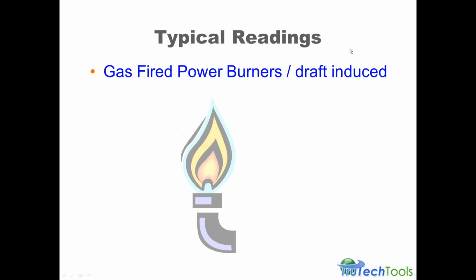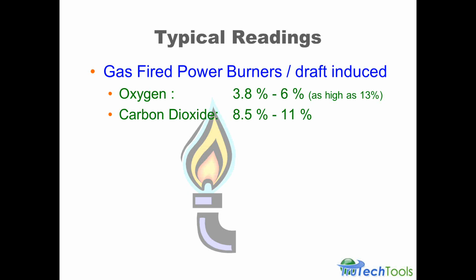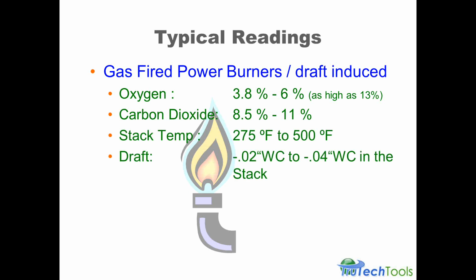On a draft-induced or power burner, the oxygen numbers do vary a bit, and here they're moving between 3 to 6 and even as high as 13% in some situations, higher levels of oxygen, with lower levels of carbon dioxide between 8.5 and 11%. Lower stack temperature readings 275 to 500, and the draft between 2/100ths and 4/100ths of an inch water column, and the carbon monoxide less than 100 parts undiluted.